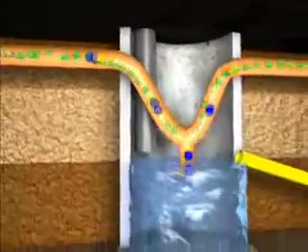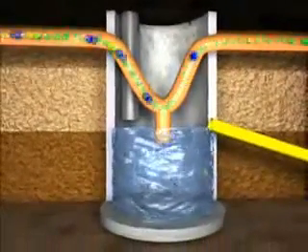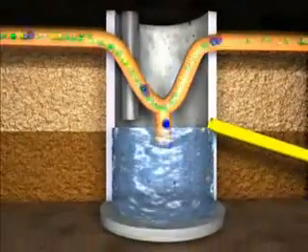It consists of approximately 50 to 70% methane, coloured green here, and also carbon dioxide, water vapour, hydrogen and hydrogen sulfide. As water vapour and hydrogen sulfide are problematic for the utilisation of the gas later, it is necessary to treat the biogas now. The gas is first freed from water vapor, coloured blue here. The condensation water is collected in a condensation shaft and pumped out.